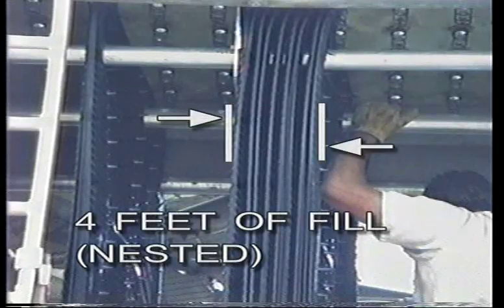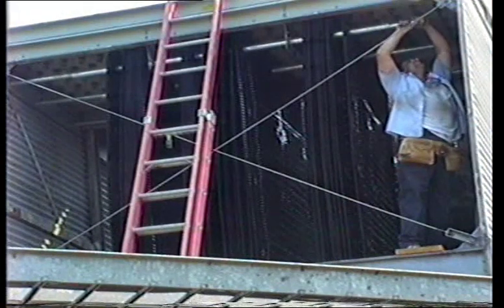Each sheet is fabricated with holes to accommodate the fill support tubes. Here we see the equivalent of 4 feet of expanded fill in its nested form. In a 12-foot cooling tower, there will be 3 such sections, which will be separated or unnested to expand across the full face of the cooling tower.